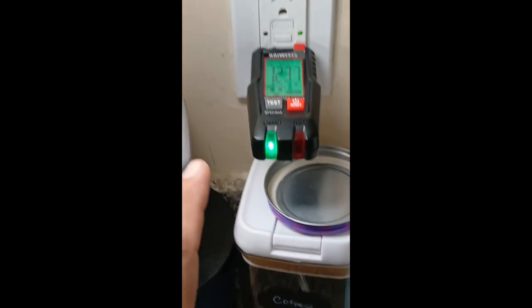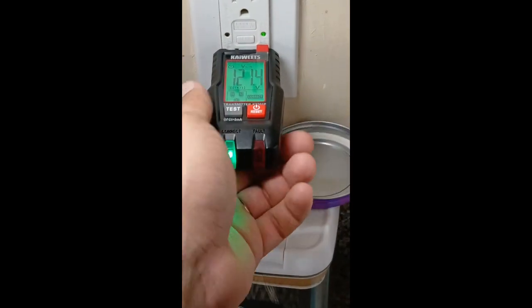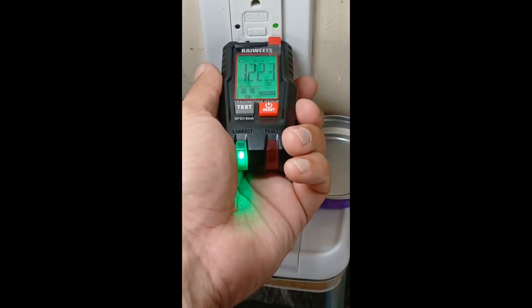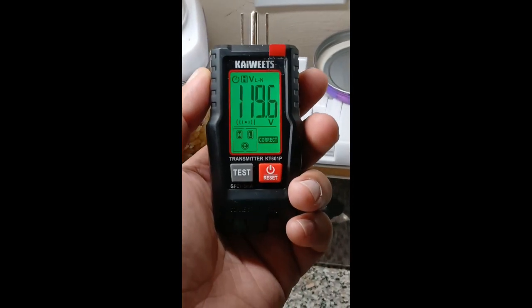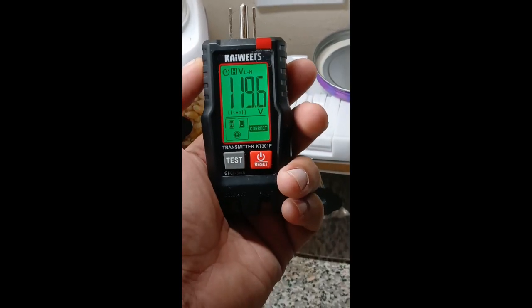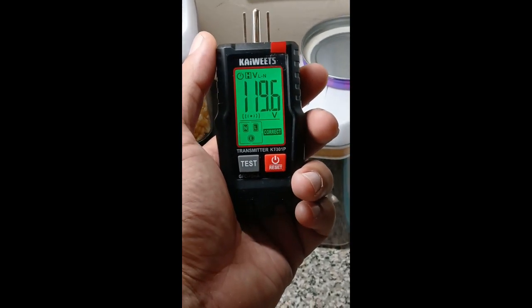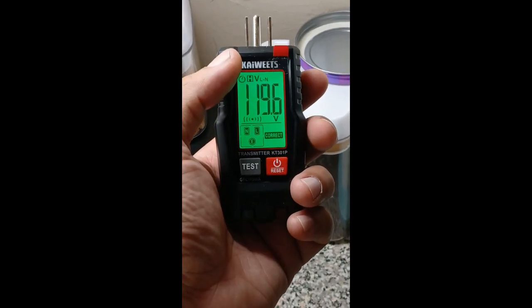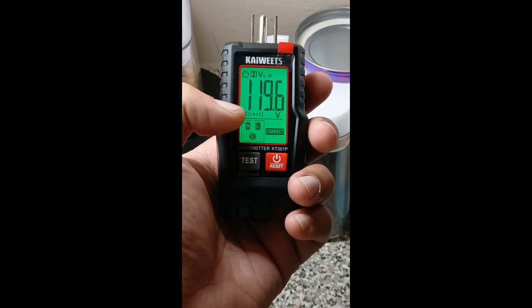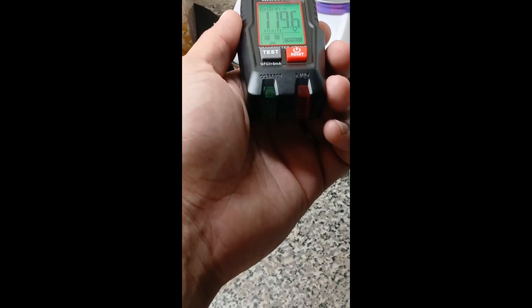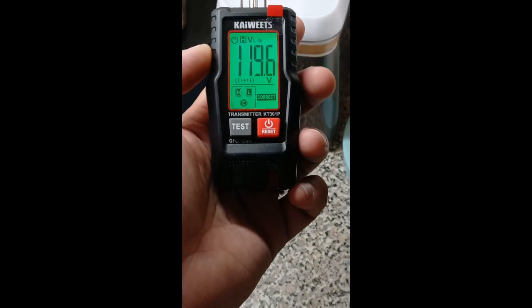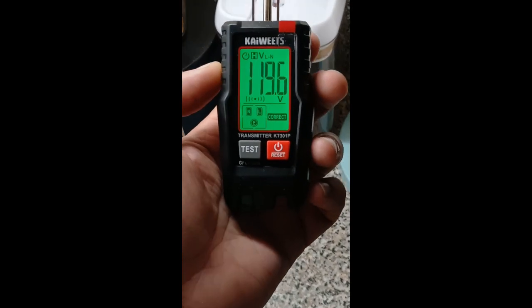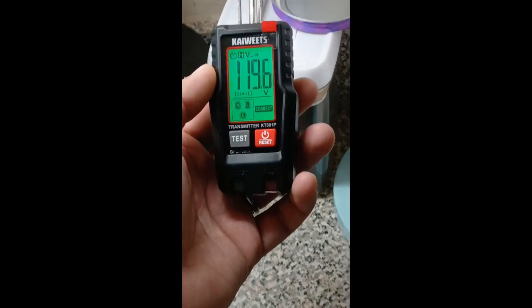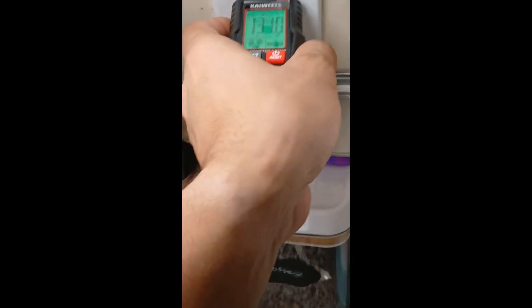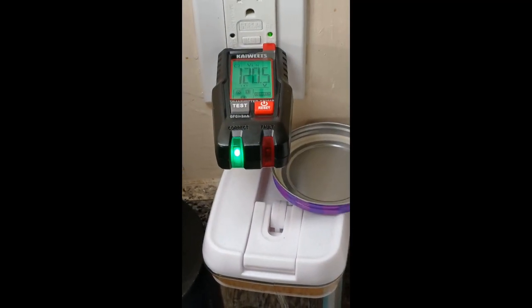Another feature, which is really awesome about this transmitter, is if you just unplug it while it's reading voltage, it's going to stay on hold at the last voltage readout on the device. Pretty cool. It even tells you if it's correct wiring. And then the service signal indicator stops flashing, and your green light flashes, indicating you removed the device. There's no power going through, but everything's on hold, and you can see and collect data off of it. All right, so let's plug it back in. And as you can see, it goes right back to reading the voltage.